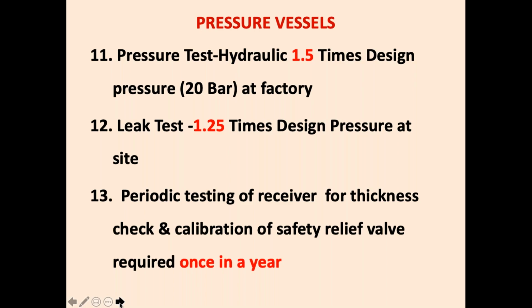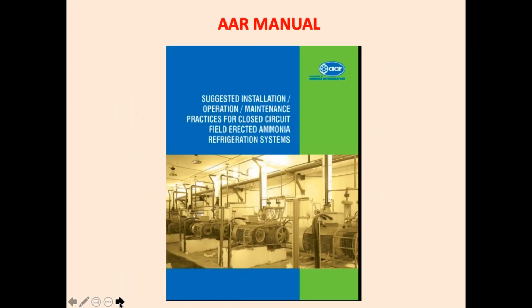So this is required. The next, this is the ammonia manual, suggested installation, operation, maintenance practices for closed circuit field erected ammonia systems. My suggestion, if you are working on an ammonia plant, follow this, and I can guarantee you that there will be no accident in your plant. I've done more than 3, 4, 500 plants. All my plants are safe. I haven't come across an accident in any of my ammonia plants.